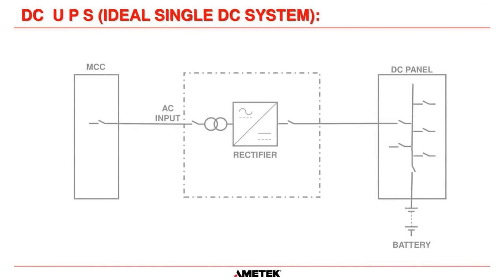here. Basically, you have to look at your DC panel and see if there is room for an additional breaker. Make sure it is rated correctly for the output rating of this charger, and then also see if you have enough room for this breaker here. Now, you'll definitely have to make sure this is rated correctly, because that will carry the full current of the battery to all of the load circuits.